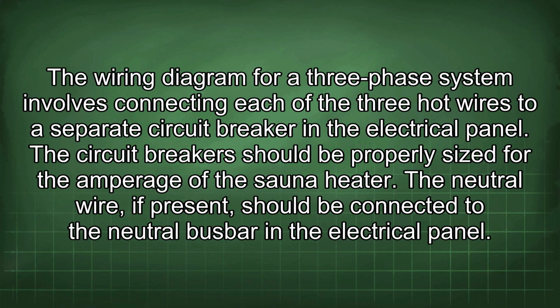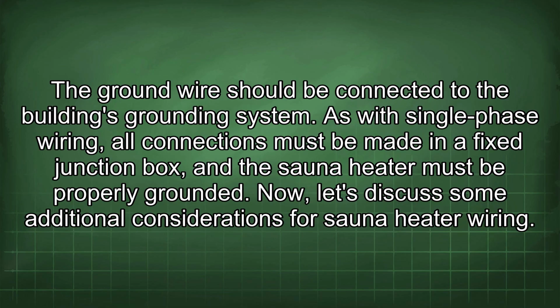The wiring diagram for a 3-phase system involves connecting each of the 3 hot wires to a separate circuit breaker in the electrical panel. This circuit breaker should be properly sized for the amperage of the sauna heater. The neutral wire, if present, should be connected to the neutral busbar in the electrical panel. The ground wire should be connected to the building's grounding system. As with single-phase wiring, all connections must be made in a fixed junction box, and the sauna heater must be properly grounded. Now, let's discuss some additional considerations for sauna heater wiring.